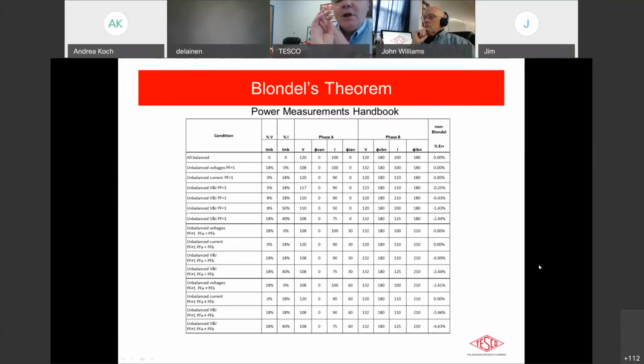All right, now, if you had a Blondel solution, would it be better? It would be a lot better. So, one of the problems that we've got out there is our 2S meters. Why were they good for so long? Well, 2S meters, the Form 2 meter comes out basically in the 1890s is really when the predecessor of it comes out. And we stick with it for now 100 and almost 30 years. And the reason we did back in the day was the equipment was very expensive. Putting 2 watt meters out on every service was very expensive. So they didn't. But back in those days, the power factor was pretty much 1. The voltage was relatively good on all 3 phases.